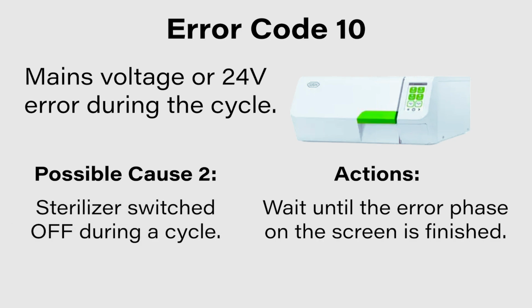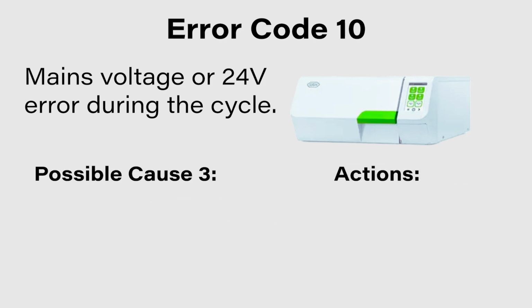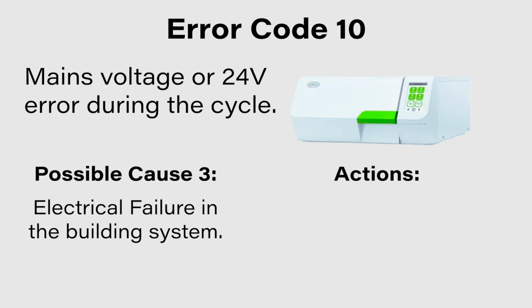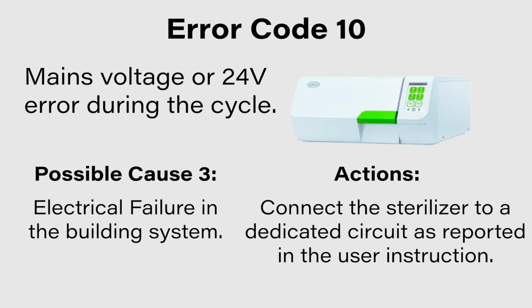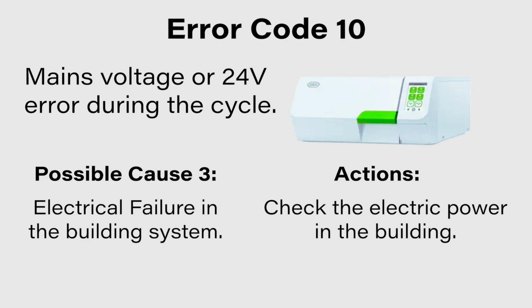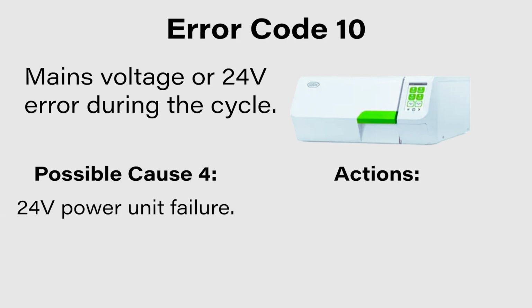For this, wait until the error phase on the screen is finished. The third possible cause is that there was an electrical failure in the building system. For this, connect the sterilizer to a dedicated circuit as reported in the user instruction. You can also check the electric power in the building and check the electric power at the wall plug. The fourth and final possible cause is that there was a 24-volt power unit failure. For this, check the 24-volt power unit.